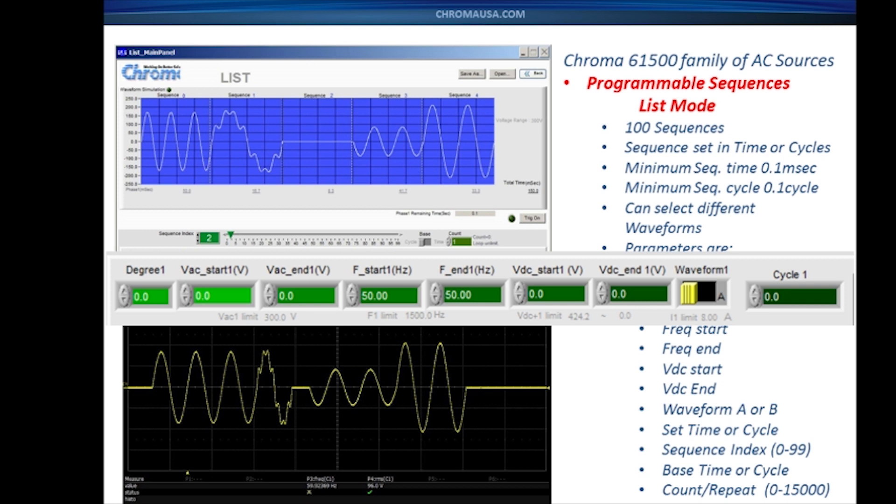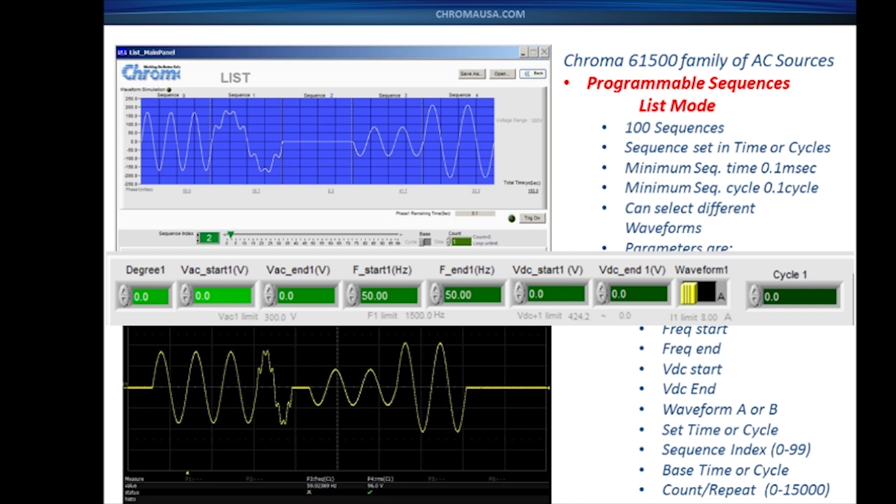Down here I've selected and ran a test for you, and I've captured it on my scope. You can see that we started off with three cycles at a nominal voltage, created some harmonic distortion for one cycle, dropped the voltage out for half a cycle, then went back to a low voltage or a sag, and then to a higher voltage or a swell. By doing this, we can see that we can easily create all of these different types of power line disturbances.